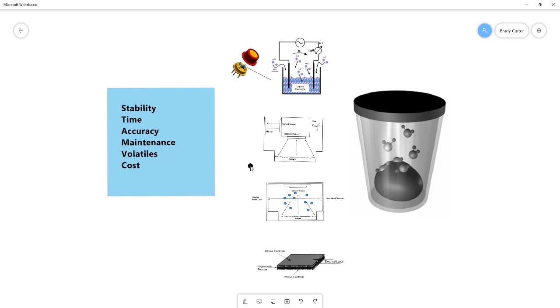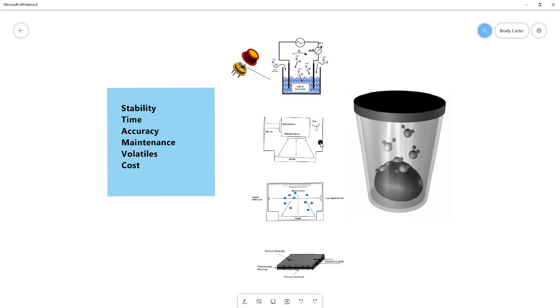When we talk about volatiles, we're talking about the influence that volatile material in a sample can have on the readings. If volatiles get inside this chamber, if the sample has volatiles, then they'll be in the chamber as well as water molecules. And that can influence the results. And in fact, it impacts all of these methods except the tunable diode laser. It is the one method that is not impacted by volatiles at all. Because it has a laser tuned to wavelengths that are specific to water, it only detects water in the headspace. The presence of other volatiles does not cause problems.